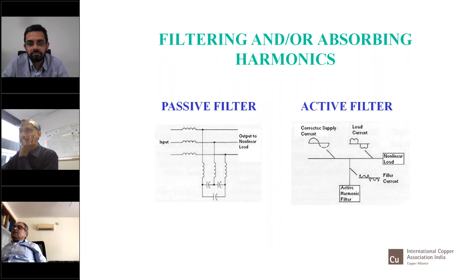They are actually harmonic generators. So whatever harmonics are there in the system, when they are connected in parallel like this, they will also generate harmonics, but equal and opposite, and they will cancel. So this is an equipment which is very frequently used, and most of the panelists here are aware of this. Use of active filters. See here, it's a wave which is coming from UPS. If you had a UPS, which I was talking about earlier, and if it was giving 30%, now you want to find a solution, what do you do?